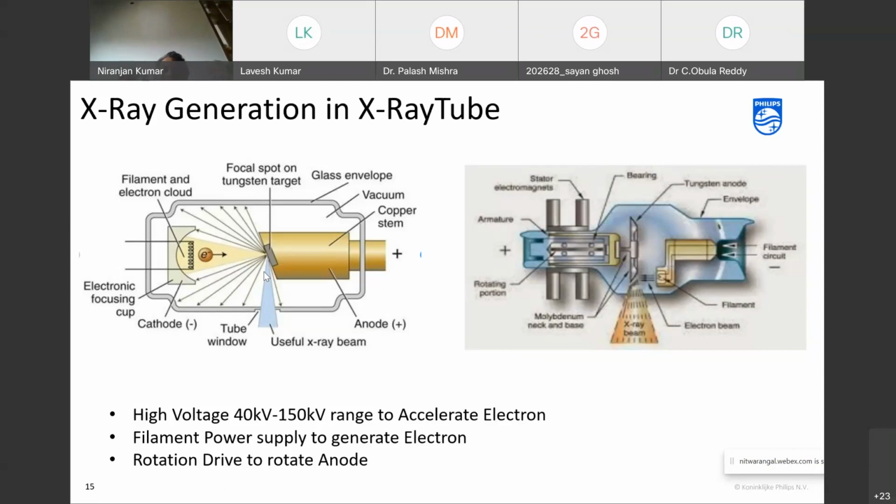The area where the electron is hitting is called the focal spot, and the focal spot size has to be as small as possible. For better imaging, you need as high an X-ray flux as possible, or as fast as possible. So you see the contradiction, which means I will produce more and more heat in a smaller and smaller area.